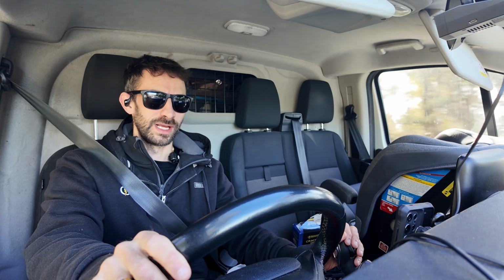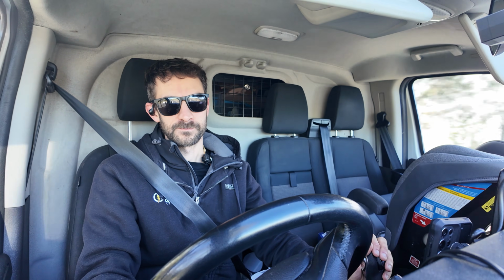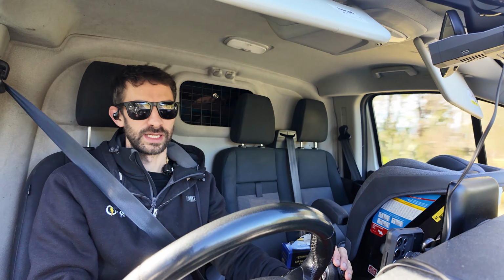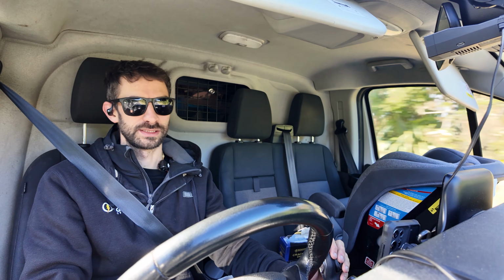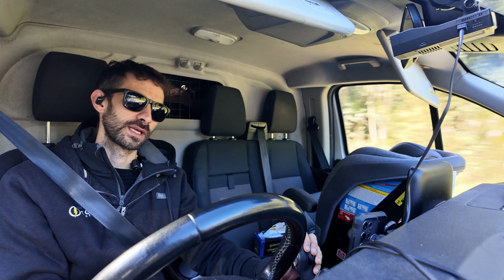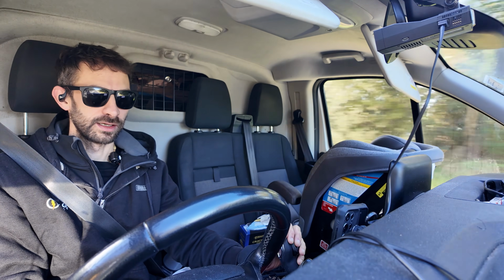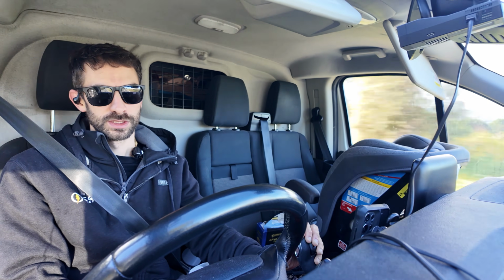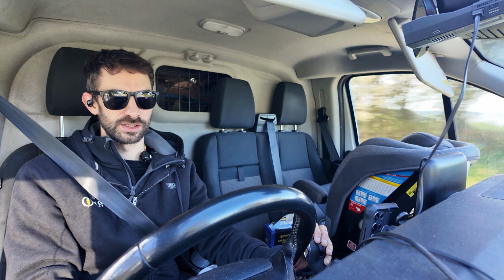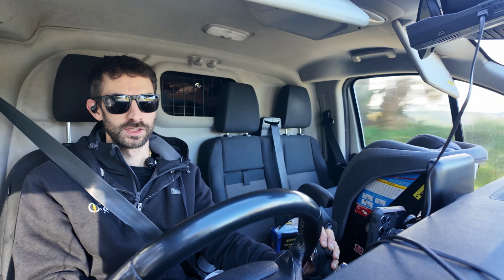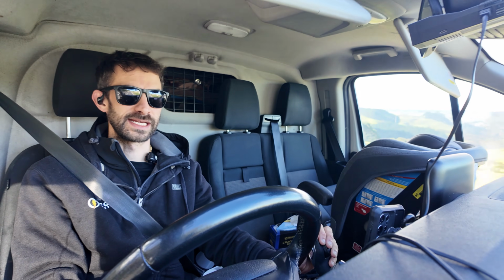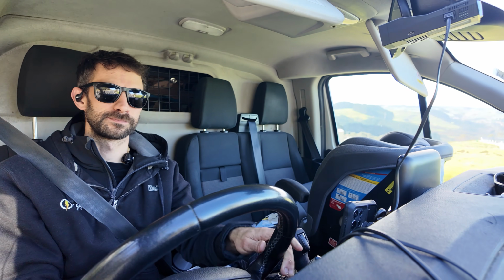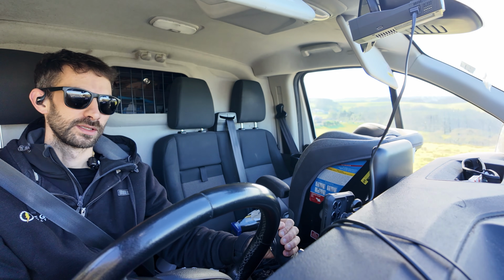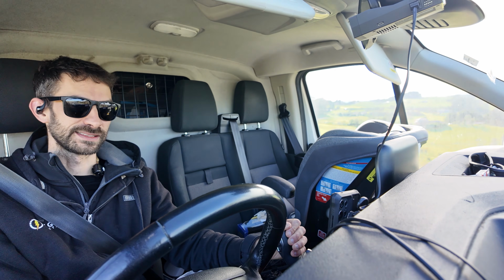So then we're left with, well, what is the earth rod actually doing? We talked about how under certain fault conditions, it just will not trip. You could have 20 amps flowing through your earth electrode because of a dead short, and that won't trip your 20 amp circuit breaker, won't trip your 63 amp HRC fuse. You need your main neutral conductor to work as a fault path. The whole MEN system only works if you have an intact main neutral coming into the installation. Without that, the protection's gone. So this is the one weakness of the MEN system.